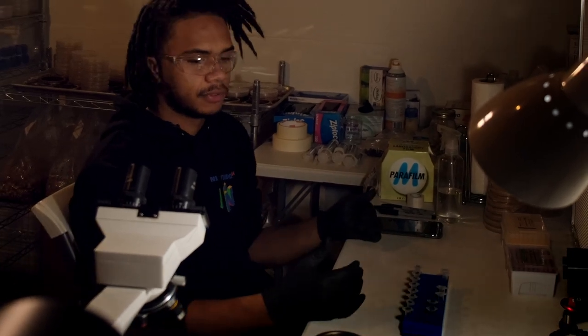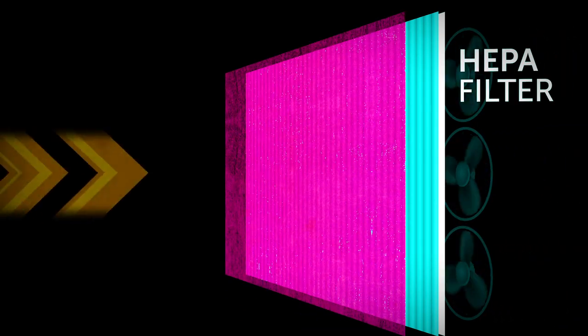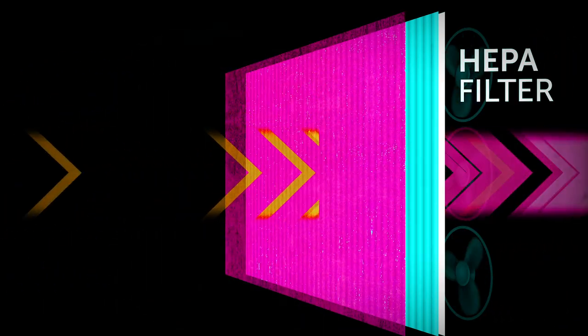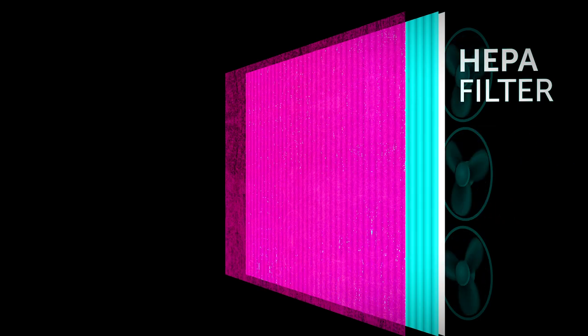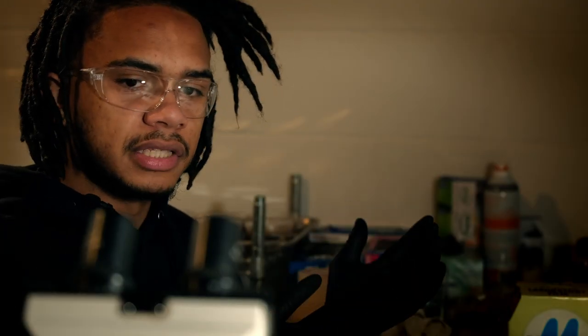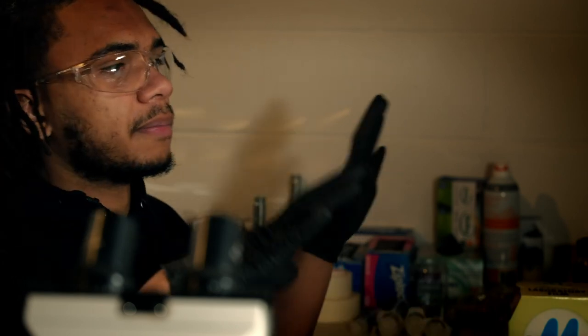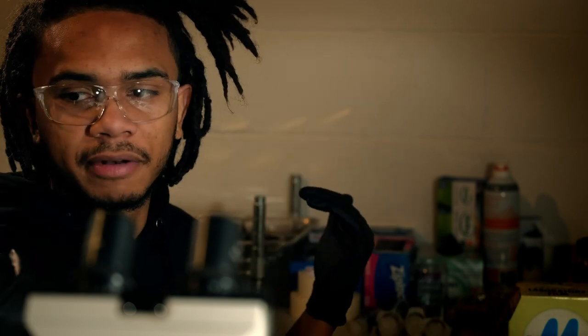So the setup I use for clean work, it's not really a flow hood. I would just consider this a HEPA filter. It has a fan in the back, it blows clean air towards me, which allows me to do clean work in front of it. I keep my table nice and clean. And then the lab has positive pressure in it. So there's always air being blown into the lab, which pushes air out of any place that air might potentially want to come in from, which keeps it clean on another level.